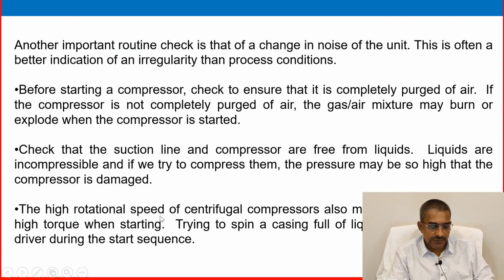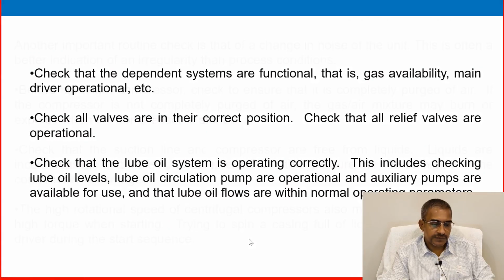The high rotational speed of centrifugal compressors also means that they develop high torque when starting. Trying to spin a casing full of liquid may stall the main driver during start sequence. Check that the dependent systems are functional, that is gas availability, main driver operational, etc. Check all valves are in the correct position. Check all the relief valves are operational. Check that the lube oil system is operating correctly.